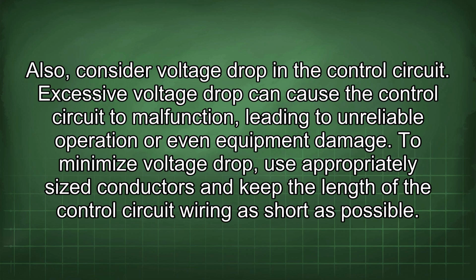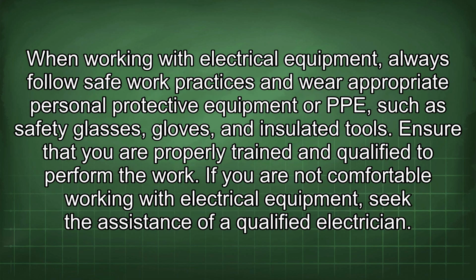Excessive voltage drop can cause the control circuit to malfunction, leading to unreliable operation or even equipment damage. To minimize voltage drop, use appropriately sized conductors and keep the length of the control circuit wiring as short as possible. When working with electrical equipment, always follow safe work practices and wear appropriate personal protective equipment, or PPE, such as safety glasses, gloves, and insulated tools. Ensure that you are properly trained and qualified to perform the work. If you are not comfortable working with electrical equipment, seek the assistance of a qualified electrician.